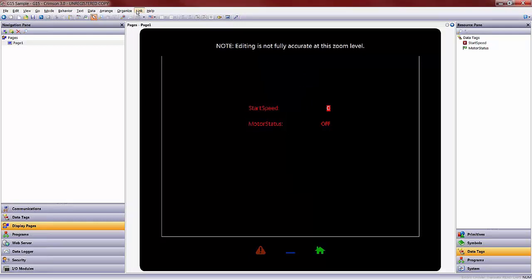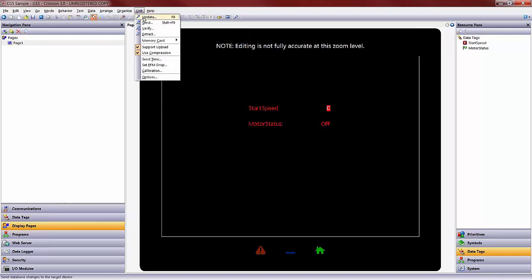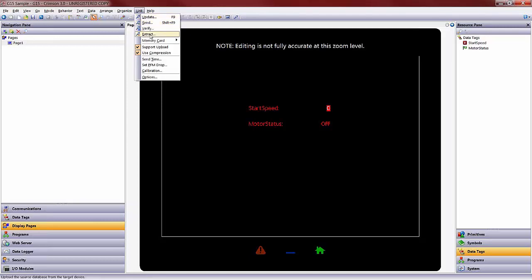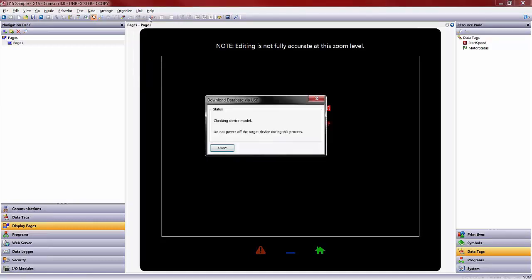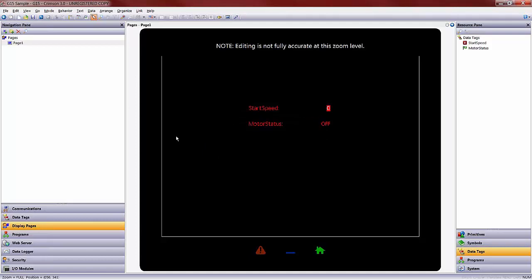And then from here, you can either hit the lightning bolt on your toolbar here, which is an update. Update means that you are sending only the changes to the screen, versus if you go to Link and Send, this will delete everything on the Crimson 3.0 capable device and send the entire program. There's also Update up here, and you can also extract files from a Red Lion device as well, or match it with a Verify. At this point, I can do either because an update in my case will also be a Send since it's a different program. Note that if you are sending a completely different program or a program for the first time, or sending a different firmware update, this download may or may not take longer to accomplish.